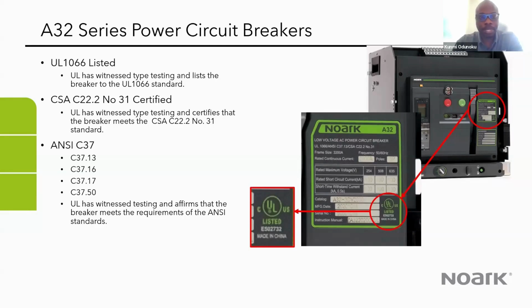So when you look at the air circuit breakers, the one that we have in the market presently, you would have the nameplate, which is in the front. There you have the UL file number and also some details about the breaker, like the frame size, the UL standard, which is UL 1066, and also the ANSI standards that it's been tested to, and also the UL logo, which is also a CUL, that's also for Canada, which has been tested to the CSA standard as well. So that's what you see when you look at the breaker from the front.